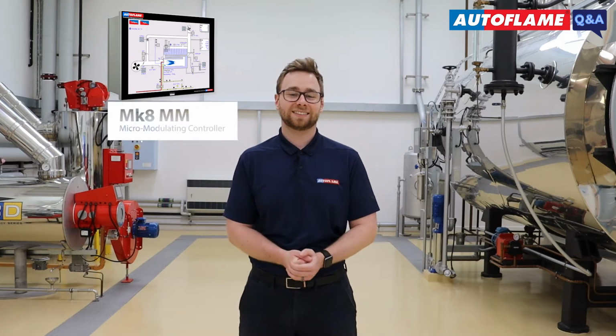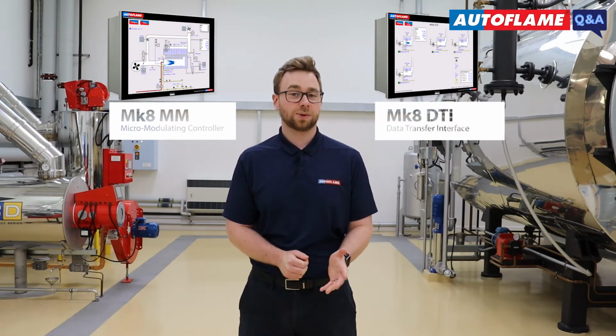The Autoflame gas and air pressure sensors have a multitude of uses, both with the combustion controllers and the data transfer interface. When used in conjunction with an Autoflame combustion controller, the gas pressure sensor is used for the purpose of gas valve proving and continuous gas pressure monitoring. The air pressure sensor is used for continuous combustion air monitoring and proving, as well as draft pressure control.